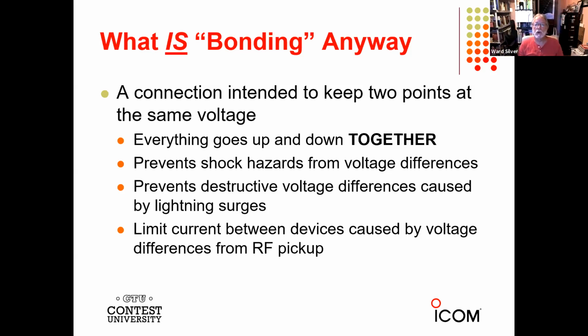When there's a current surge or some kind of lightning or a fault, you don't want this point to suddenly be 6 kilovolts above this point. And if you can keep everything at the same voltage, what causes current to flow between 2 different points? Voltage. So you can minimize current flow by minimizing voltage differences. Bonding in the AC world prevents shock hazards from voltage differences. If you bond all your equipment together with suitable conductors, then it's all going to be at the same AC voltage, even if there's a short circuit. So the idea is to prevent you from getting a shock when you put one hand on one thing and one hand on another thing. You don't want there to be voltage differences there.